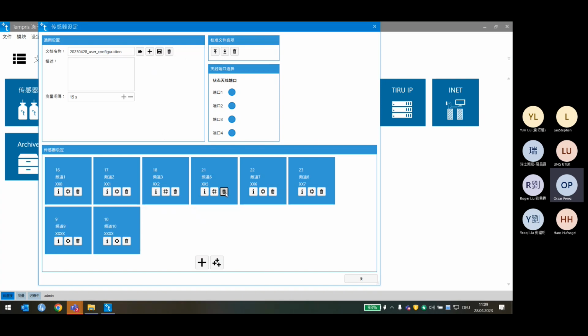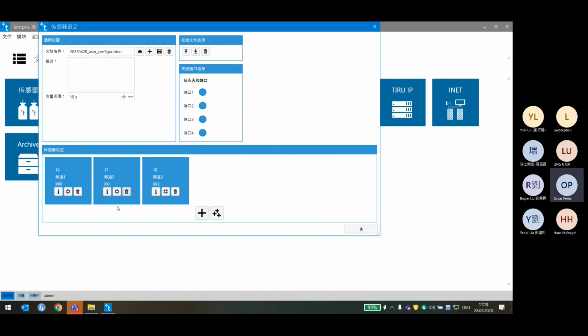So we will configure the 3 channels that we are using, save with another name, and configure the file with these sensors. Otherwise, the system tries to find sensors which are not available in the freeze dryer, which is a performance consumption that is not required and not recommended.